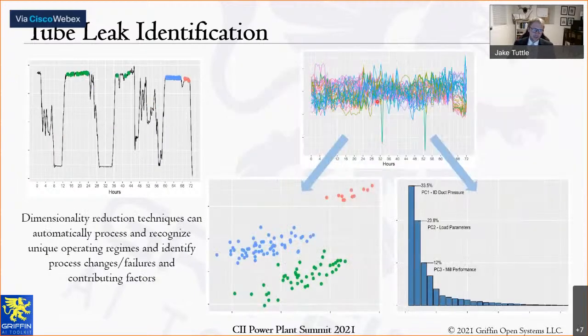What our tools do is break this information apart into very easily identifiable regimes, recognizing that here, this is normal operation. Here, likely the tube had a pinhole leak and was starting to get close to erupting and failing. And in the red, you see it's an entirely different operating regime, meaning that these parameters indicate something had happened inside of the unit, which was a tube leak. So almost 12 hours before the unit actually identified the failure and came offline, we were able to know that there was a problem long before operations would have traditionally.